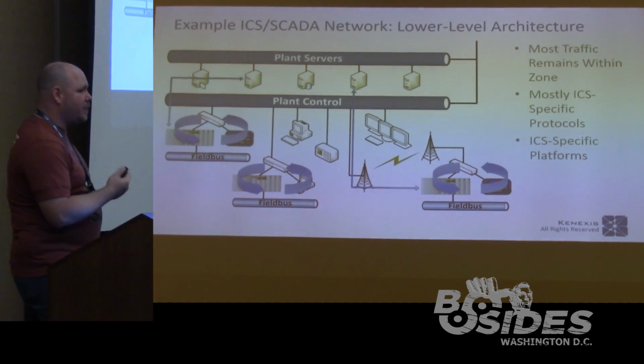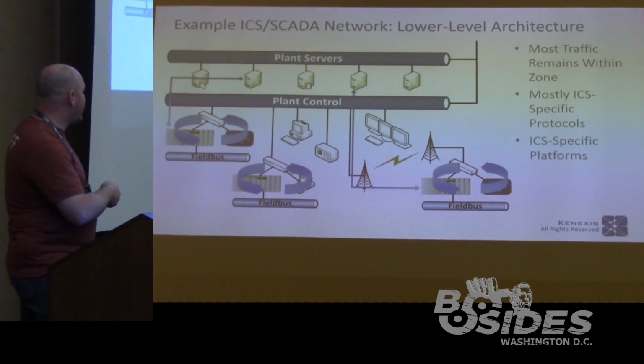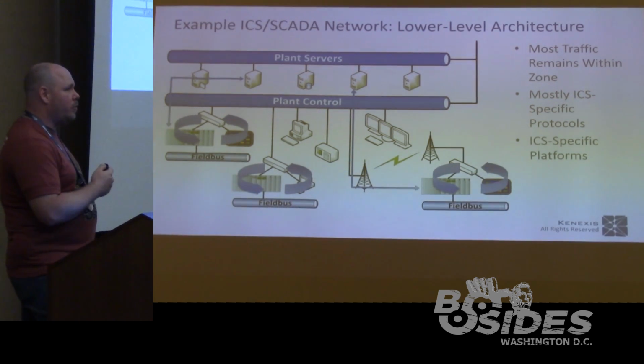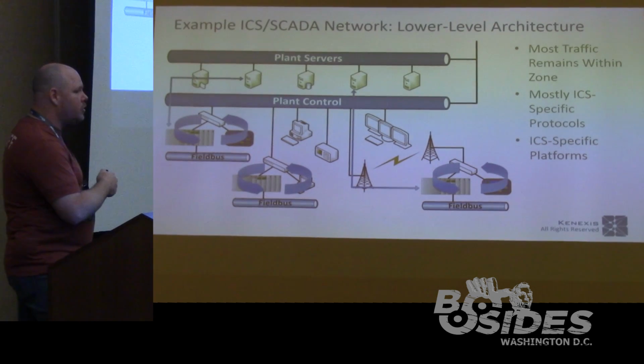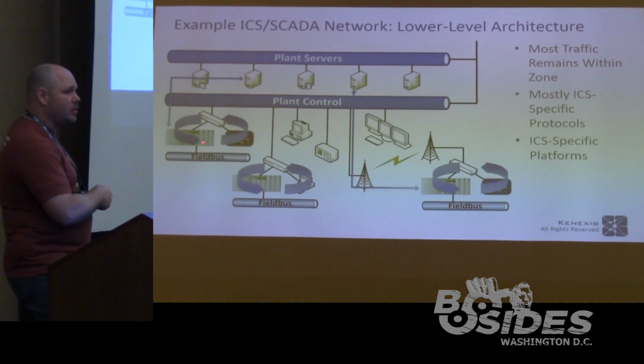The way we typically set it up, each one of these is a separate VLAN, specifically for performance reasons, because these systems have to stay up and run continuously all the time, and determinism is much more important than security. So they would much rather deal with the VLAN stuff. Yes, you can do trunking, and yes, you can monitor things, but a lot of times these are layer 2 switches. They're not smart enough to do the VLAN trunking you can do up at layer 3 routing-type switches.